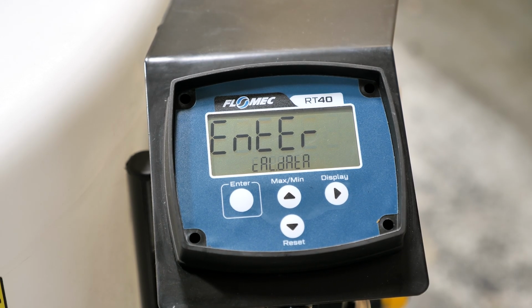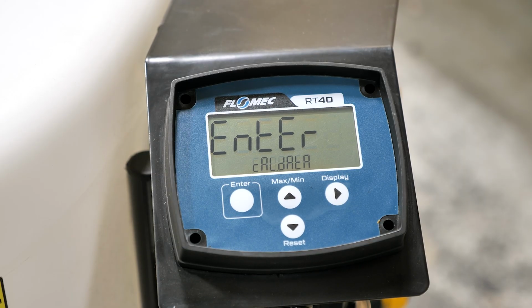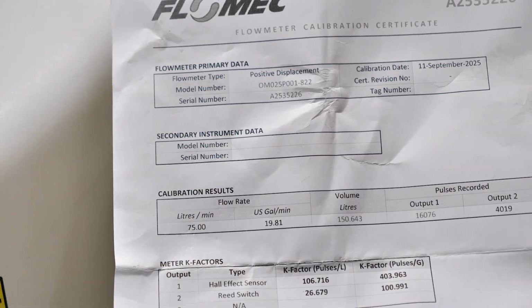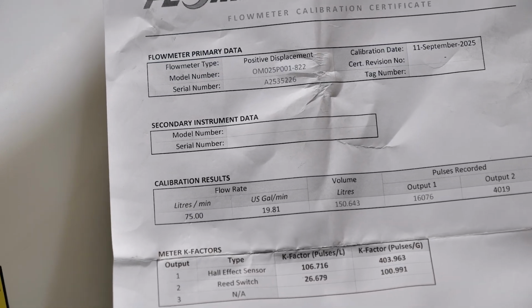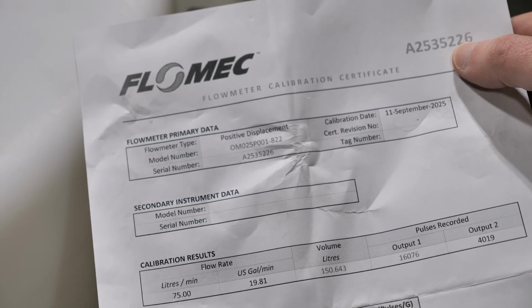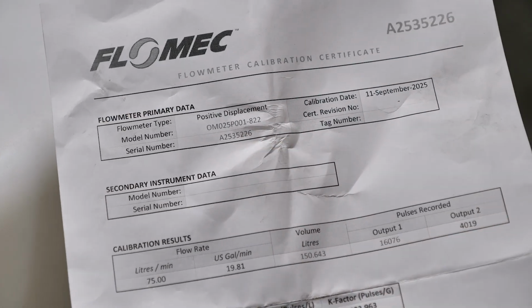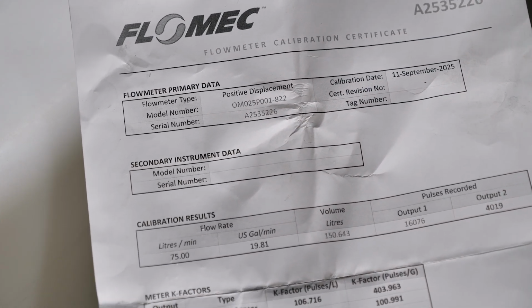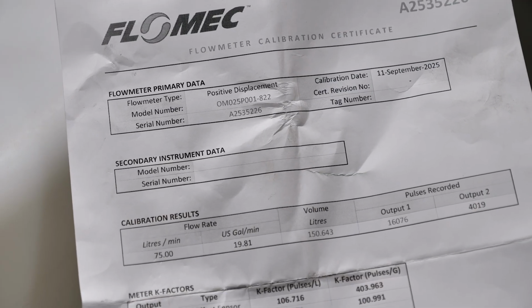The next one you have to do is your calibration data. So calibration data is very important. It is what makes sure that you are always metering correctly. Every display has to be programmed or paired with the flow meter itself. So with your flow meter, you're going to get a calibration sheet that looks like this. On the top, it has a serial number here, and on your flow meter itself, you should have the flow meter have that serial number.